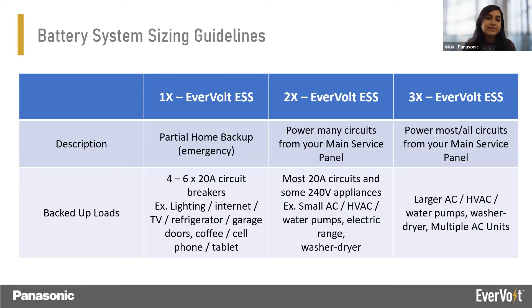Like, what is the total current consumption of all the different types of loads connected to the system, especially when it comes to inductive loads, such as air conditioning units or pumps, wherein the initial startup current can be very high and can be more than what the inverter can handle. So during an outage, it may trip. So that's why load sizing becomes very, very important when designing the system. Next slide, please.